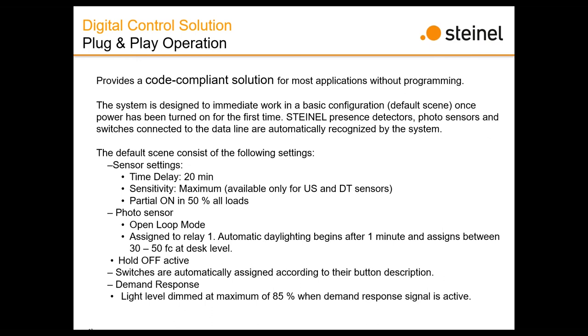The photocell, it automatically recognizes that there's a photocell connected to it, it selects it for an open loop type of function, and it assigns it to relay 1. After about 1 minute, it analyzes the room as soon as it's powered up. After about 1 minute, then the daylighting will begin, and it will give you desktop level at somewhere between 30 and 50 foot candles.